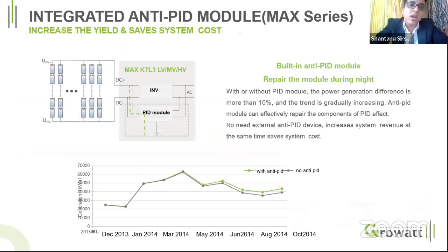We also provide an anti-PID module in the Max inverter, and for all series as an optional feature. The main use of anti-PID is to reduce potential induced degradation at the module level. There are two options: the PID can work only at night as per your requirement, or throughout the day, and these settings can be done in the inverter itself. However, it is an optional feature and needs to be told to our salesperson before placing the order, since the inverters currently in the Indian market do not include the anti-PID module.